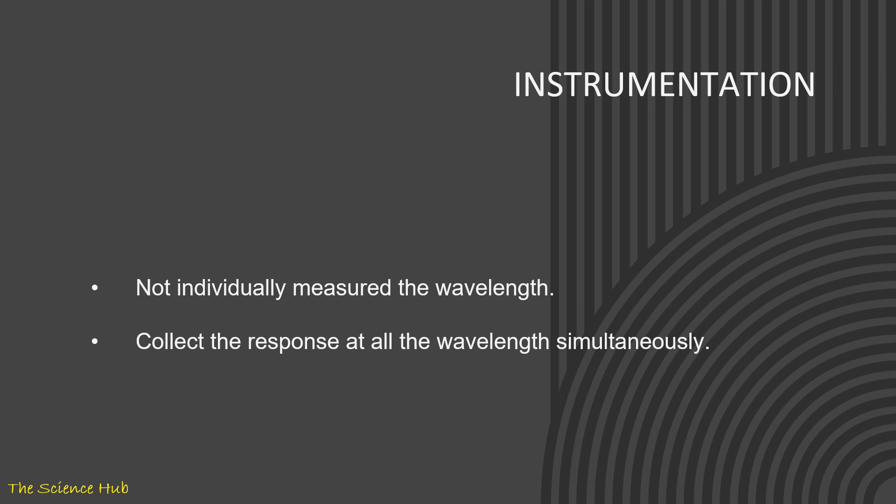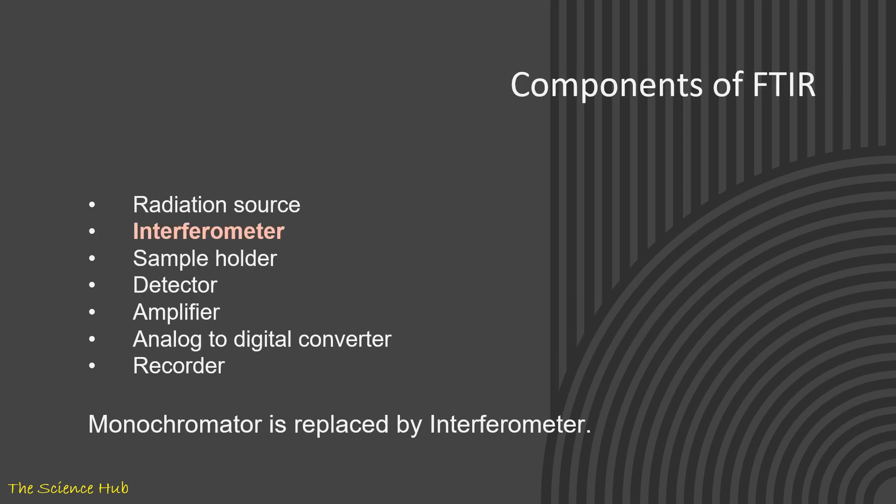Instrumentation: not individually measuring the wavelength—it collects the response at all wavelengths simultaneously. What are the components of FTIR? Radiation source, interferometer, sample holder, detector, amplifier, analog-to-digital converter, and recorder. Here you can observe that instrumentations or components are the same as IR spectroscopy, but one thing is interferometer. Instead of monochromator, here we are using interferometer, and it plays an important role in the spectroscopy.